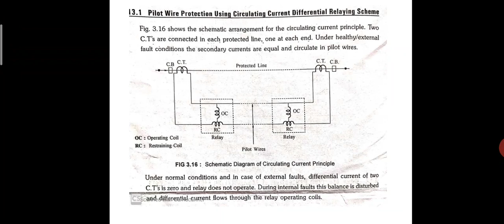This is the circuit diagram, the schematic arrangement for the circulating current principle. 2 CTs are connected on the protected line, one at each end. Under healthy or external fault conditions, the secondary currents are equal and circulate in the pilot wires. Under normal condition and in case of external faults, the differential current of the 2 CTs is 0 and the relay does not operate. During internal faults, this balance is disturbed and differential current flows through the relay operating coil.